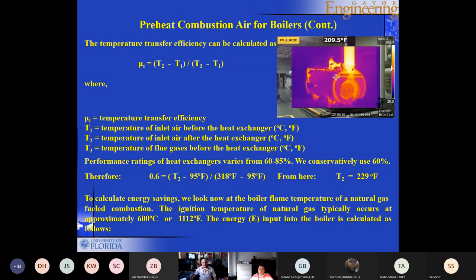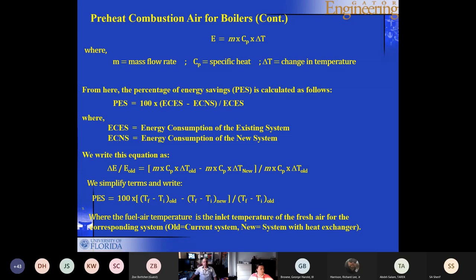And as a consequence, if you go to the next slide, it will show you how to calculate the energy savings. If you take that mass flow rate times the specific heat times delta T, the mass flow rate, of course, is m, the Cp is the specific heat, and delta T is the temperature change. You can compute a percentage of energy savings, which is the energy consumption of the existing system minus the energy consumption of the new system, divided by the energy consumption of the existing system.